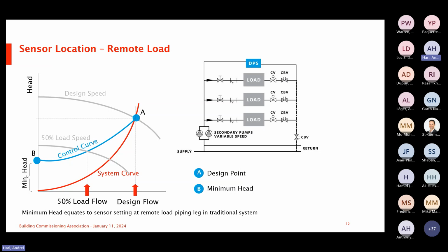The point being is that once the DP sensor is located in the system, and if there are issues, that DP sensor is fixed. So you have to relocate that DP sensor if you can't calibrate it to deal with that issue. Okay, so that's where it becomes a challenge. As we get to the end of this, I'll give you an application where we had a challenge like this for a Toronto housing project ourselves, where they incorporated the DP sensor and located it at the most hydraulically remote load in the system, and two of the risers weren't being satisfied. As we go through, I'm going to show you how the sensorless technology was able to address that at the panel without having to worry about the mechanical location.